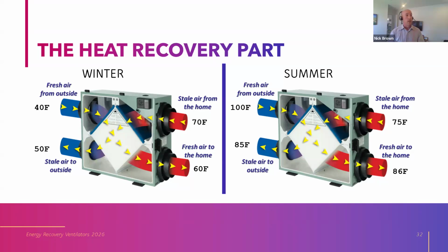In summer, on the other hand, you might have 100-degree outside air. Using the stale 75 indoor air, you're able to bring that down to 86 before you have to cool it. Does that make sense? And that's where the energy savings are coming from. Now you're having to run two fans in an ERV situation, right? One exhaust, one supply, whereas an exhaust or a supply ventilation strategy just has one fan. So you're trading extra ventilation energy for saving heating and cooling energy.